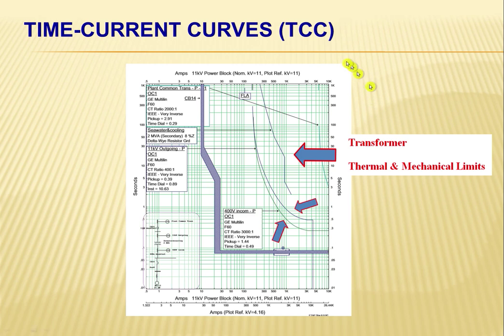Also here, this is the curve of our circuit breaker. All of these three curves are on the left side, meaning we have performed proper coordination between our transformer and our protection relays. This relay is for the primary side of the transformer; we did not tackle this one. Later on, in our next video, we will also be discussing a relay setting calculation for our upstream relay for the primary side of the transformer.